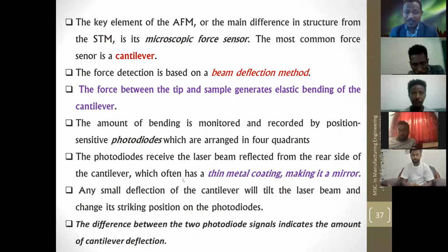On the other hand, the cantilever beams should be thin metal coated materials, making it a mirror surface, and any small deflection of the cantilever will tilt the laser beam to another direction. So you will get distortion of the image of your atom surface. So the correct positioning of the cantilever should be there.